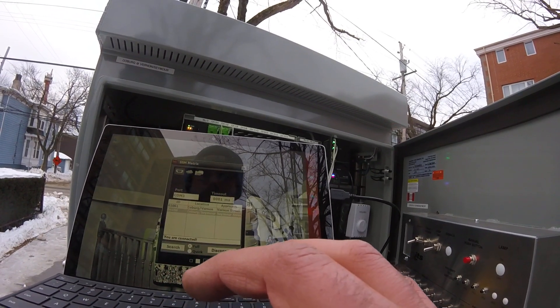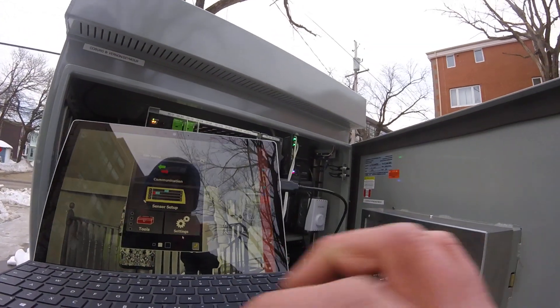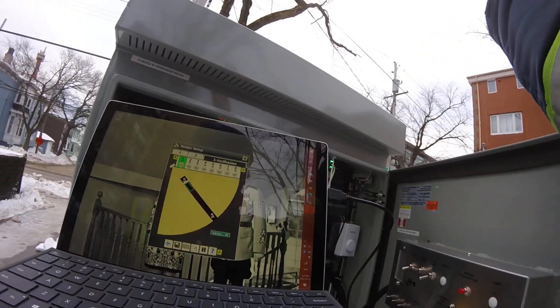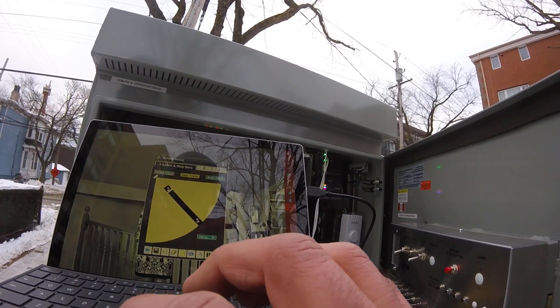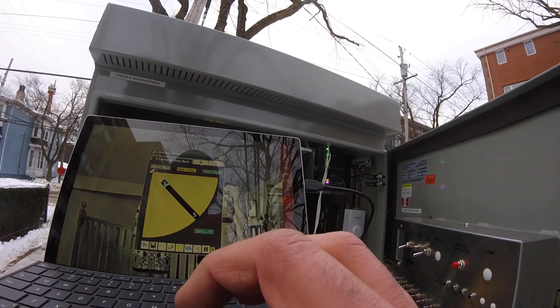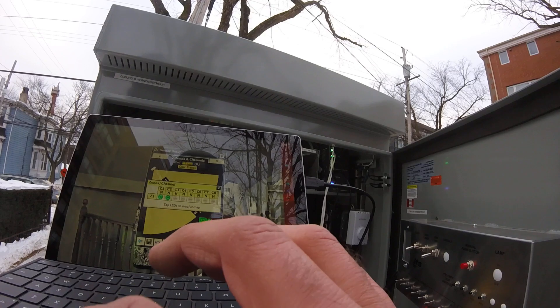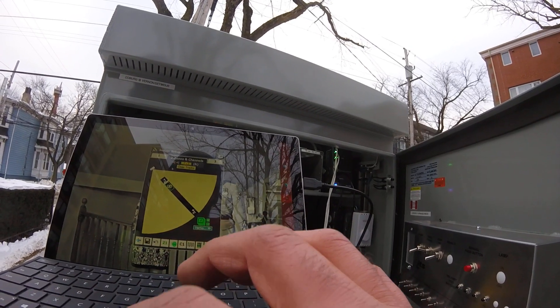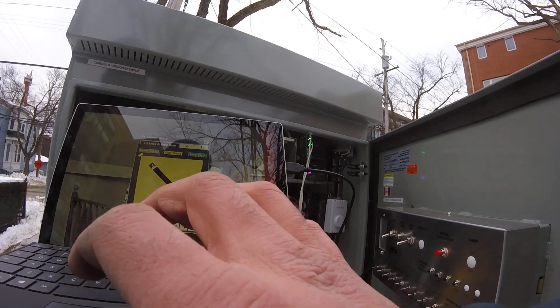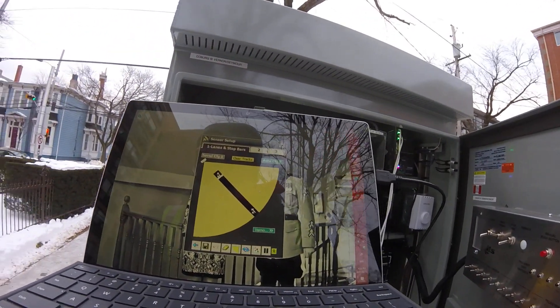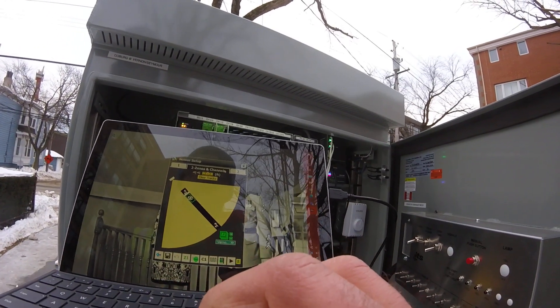So we'll go back and disconnect. We're going to connect to Vernon Street. So right now there's a vehicle next to the stop bar, but that shouldn't change the light because they're not triggering the sensor. I just made sure channel one and two was selected on there. This one's also already set up — it was having an issue where it wasn't picking up bicycles, so it should only pick it up if somebody's on the detection zone for 10 seconds.